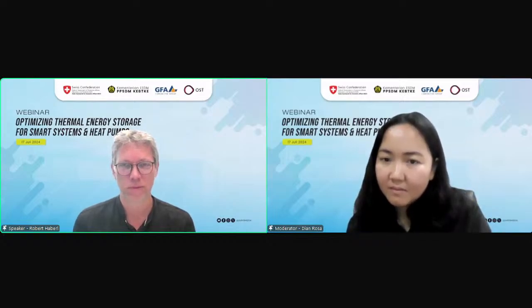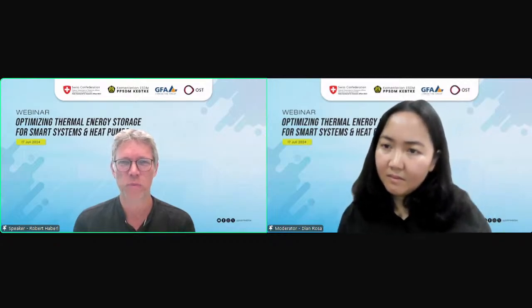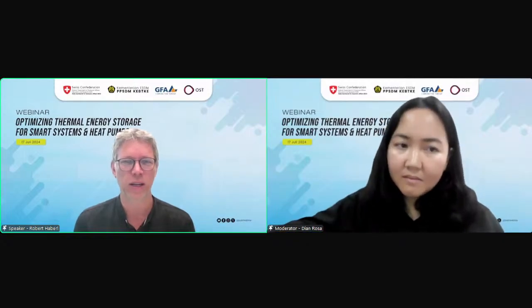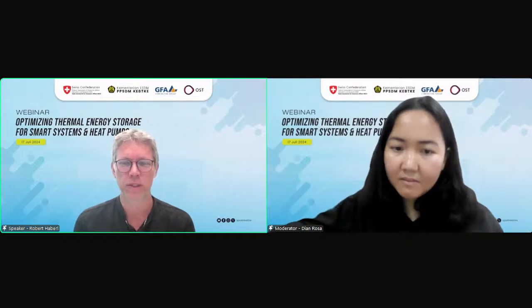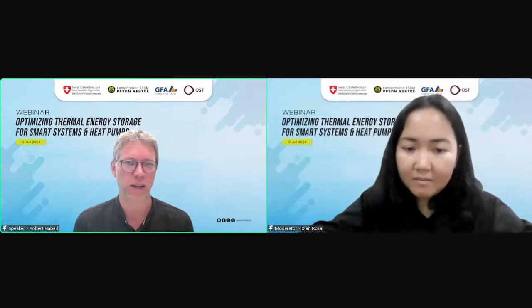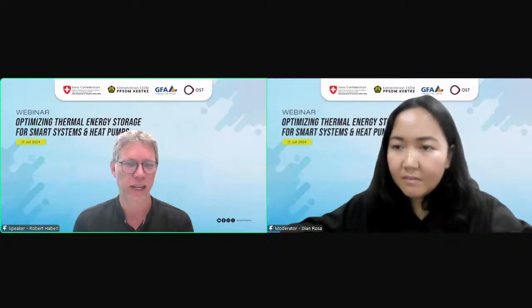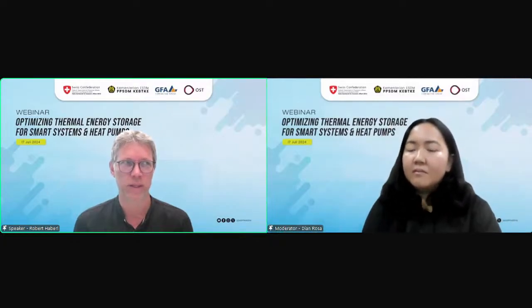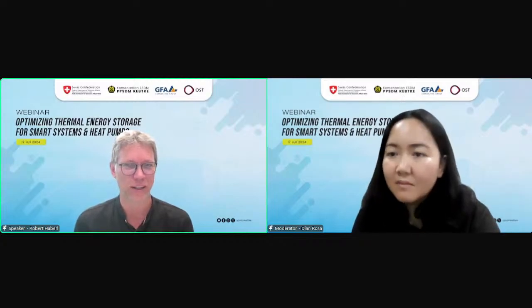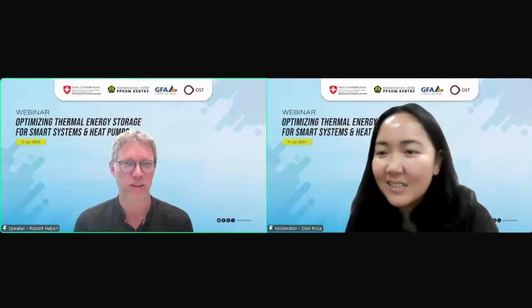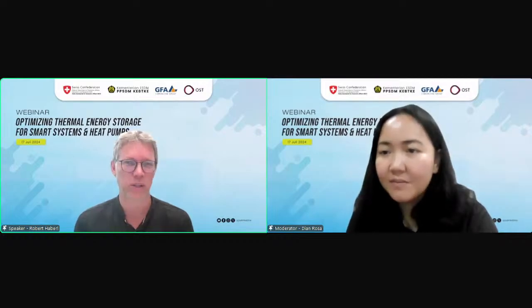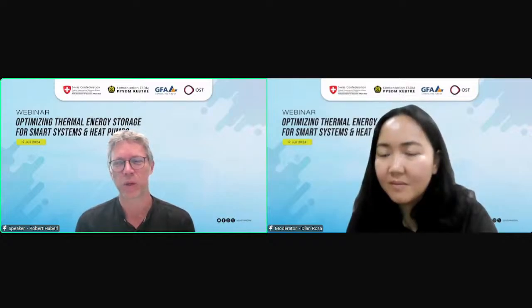But solar thermal heat is a very good solution. A solar collector with an absorber made of a metal sheet coated with a coating that collects heat, covered with glass to prevent heat losses, produces heat directly from sunlight with high efficiency, and you can connect that to your storage tank. You don't have to have a heat exchanger — you can have the same liquid in the storage tank and in the collector. Here in Switzerland it's usually water with antifreeze additives, but that's not necessary in Indonesia. You can use pure water without a heat exchanger; the solar thermal collector produces heat and stores it in a tank without going through electricity.